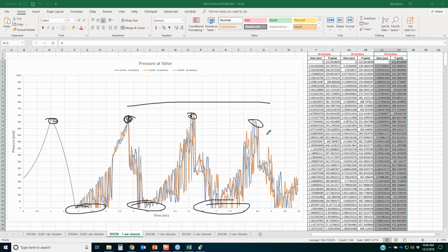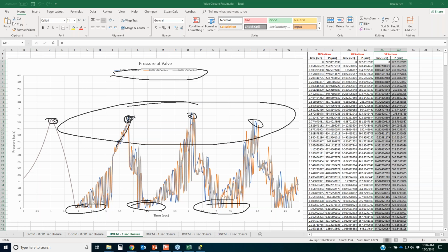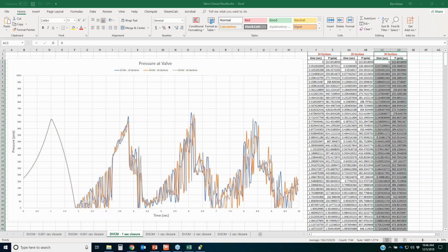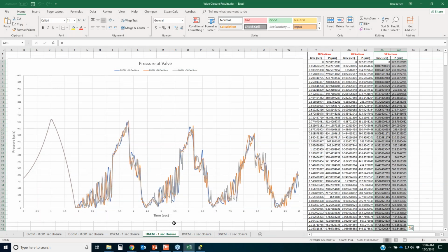So these may be fairly realistic, especially because when I use different amounts of sectioning, you can see how the pressure values rise up to that value over several time steps. If you do a comparison with the discrete gas cavity model, it's similar. Again, gas cavity model, less noise. But again, you're still cavitating. The goal is don't cavitate.